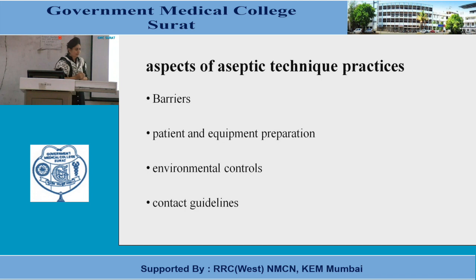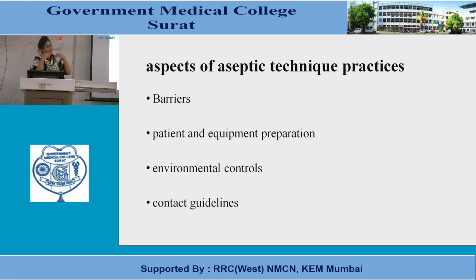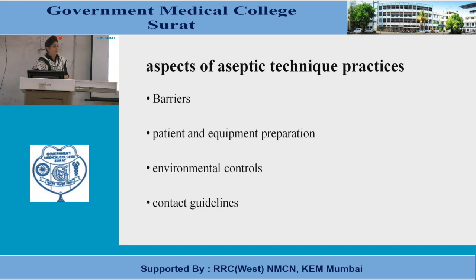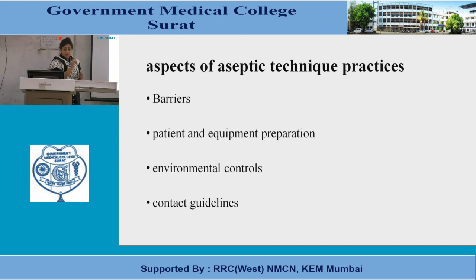Major surgeries and important invasive procedures are done in operation theaters because we get a relatively microorganism-free environment. The OT has zones: an outer zone, a clean zone in the middle where recovery happens and patients are changed, then the sterile zone where nobody enters except those in surgical clothes and footwear, and then the operation zone — the absolutely sterile zone with HEPA filters and filtration systems making the environment microorganism-free.